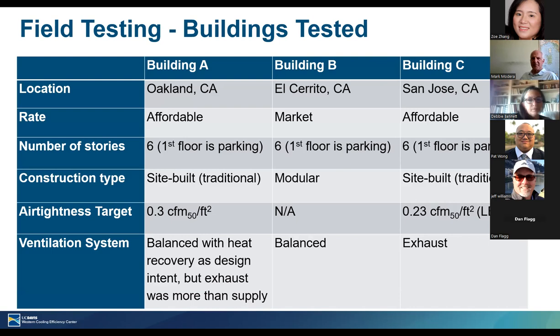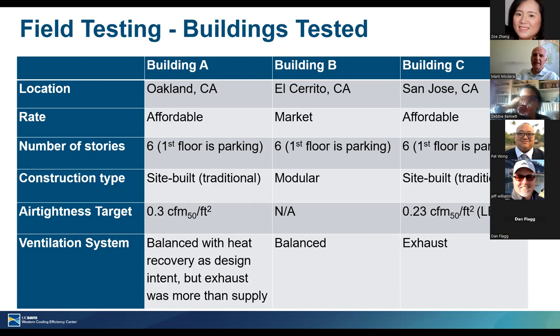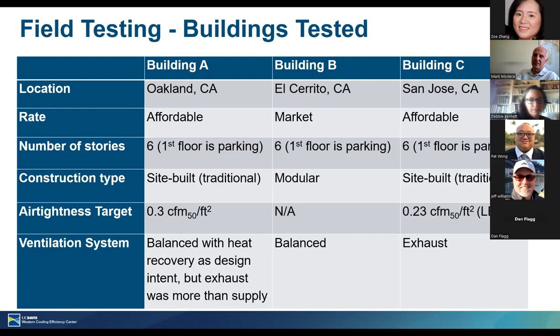Now let's switch over to field testing. We tested three buildings, all in the Bay Area — one in Oakland, one in El Cerrito, and one in San Jose. Two were affordable housing and one was market rate. They were all six-story with the first floor set aside for parking. Two were site-built conventional construction and one was modular. Two were trying to meet air tightness targets — one the California Title 24 value, one the LEED value — and the third had no leakage target as part of its design.